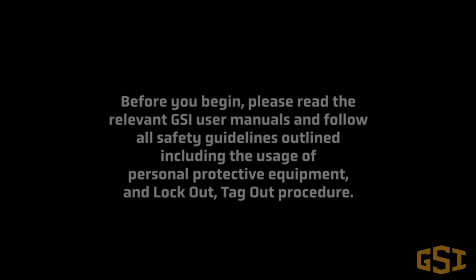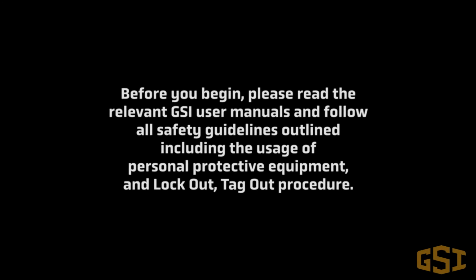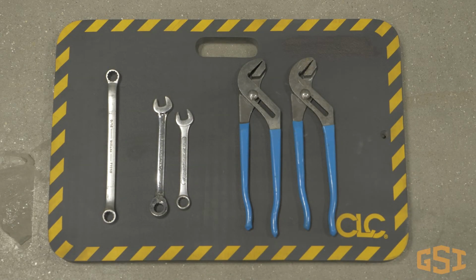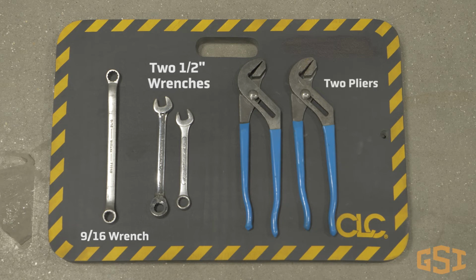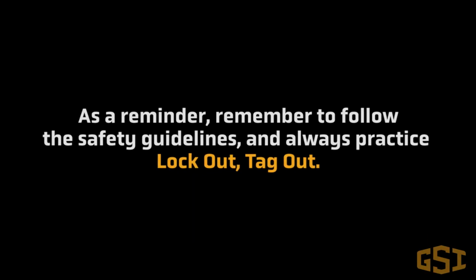Before you begin, please read the relevant GSI user manuals and follow all safety guidelines outlined, including the usage of personal protective equipment and lockout-tagout procedure. To perform this service, you may need the following tools: a 9/16 wrench to remove the side heater panel, 2 wrenches to adjust the flame probe mount, and 2 pair of pliers to adjust the angle on the flame probe. As a reminder, remember to follow the safety guidelines and always practice lockout tagout. If you have questions about lockout tagout, we have a video for that too.